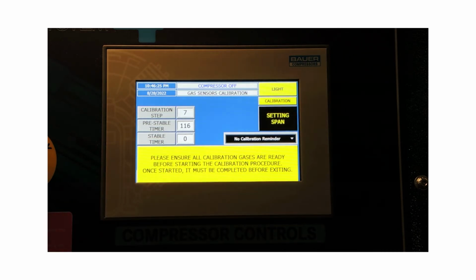that 2 minutes. Unfortunately we don't know if we're flowing gas because the program at this point doesn't tell us what our pressure is. That's why before we start the calibration we want to verify that both cylinders of test gas have enough pressure in them so that we can go through a complete calibration procedure. So double check that, and if you don't have enough pressure, make sure to call your distributor, call Bauer, and order those gases before you continue on to the calibration procedure. I'm going to go ahead and catch up here in a minute.